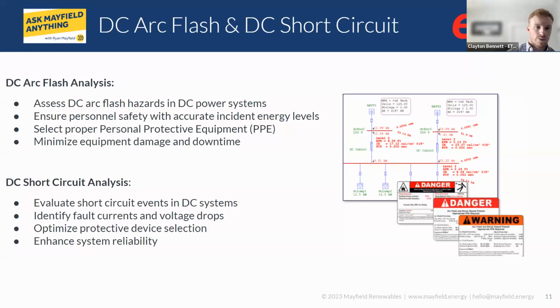Now I want to talk briefly about the short circuit module. ETAP facilitates DC short circuit analysis to evaluate the behavior of protective devices during a short circuit event. And some of the advantages of using ETAP is you're able to evaluate system fault conditions and assess protective device ratings for direct current systems.